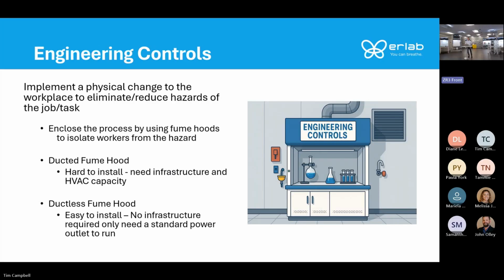So when you are working with chemicals and you think of an engineering control to reduce exposure to the chemical, most of us think of a fume hood. And if you think of a fume hood, you're probably thinking of a traditional ducted fume hood. That's probably what you're used to using. It's a fume hood enclosure where the chemical vapors are pulled away from you. And then that fume hood is connected to ductwork and a fan that's going to take those chemical vapors and blow them outside. It makes it the outside world's problem. All those chemicals are used.